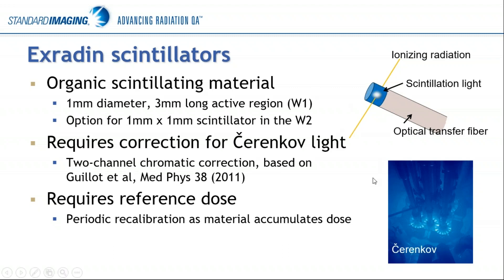We do have to correct for Cherenkov light. This is a classic Cherenkov picture of looking into a reactor coolant pool. Cherenkov light is light generated by electrons traveling faster than the speed of light in the medium — it's kind of a light shock wave, just like a sonic boom is a sound shock wave from a jet traveling faster than the speed of sound. This is generated in our optical transfer fiber, so it is a field size dependent stem effect. We correct for this using a two-channel chromatic correction based on a publication from Guillot et al.